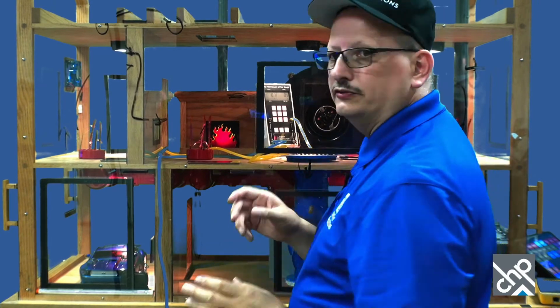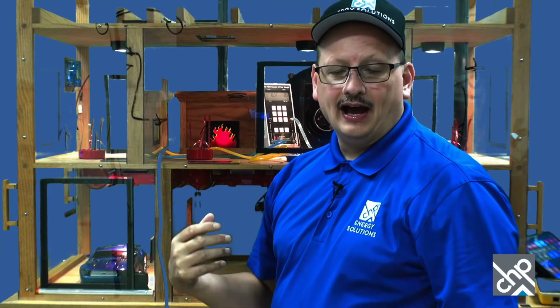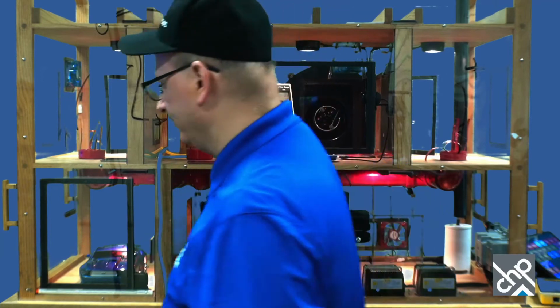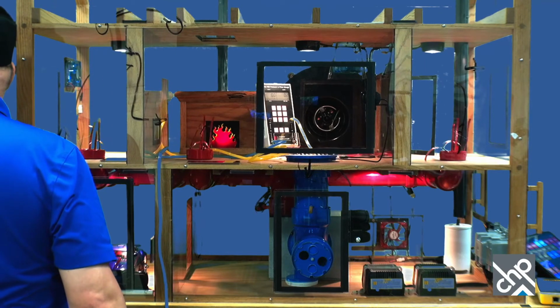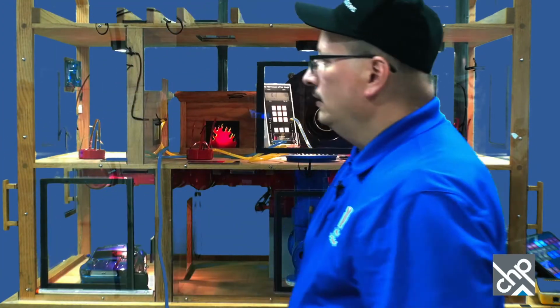So now I'm going to close the door, and ideally when I close the door now, the air would go through those vents or louvers and not be trapped behind the door. And the smoke should still go out the chimney even though the door is closed. So now you can see there, even though the door is closed, the smoke is still going out the chimney. It's dropped some. So I probably could have put some more relief there. But anyway, you get the idea that you want to do this if you have air trapped behind the door.